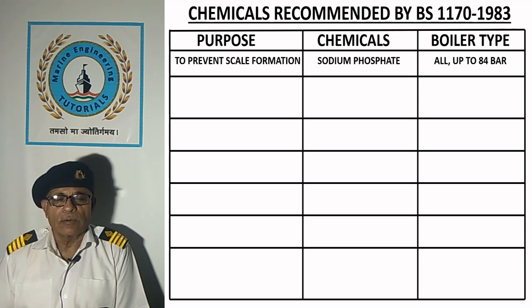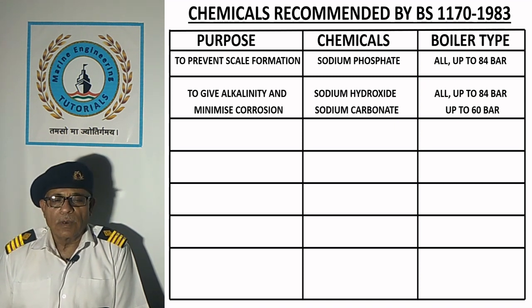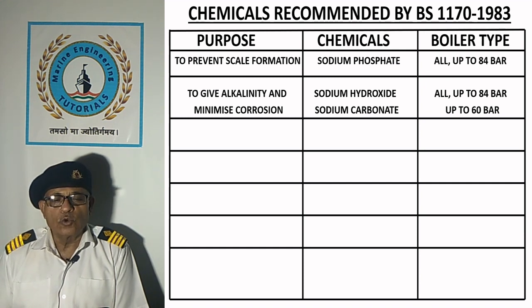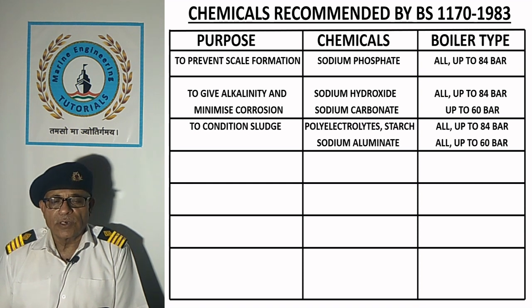First, to prevent scale formation, sodium phosphate is used for all boilers up to 84 bar. To give alkalinity and minimize corrosion, sodium hydroxide is used for all boilers up to 84 bar, and sodium carbonate for boilers up to 60 bar. To condition sludge, poly electrolytes, starch and tannins are used for boilers up to 84 bar.